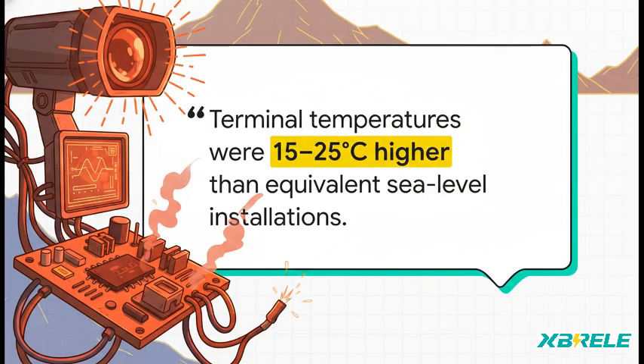And on the heat side of things, the evidence is just as dramatic. Thermal cameras at some of those Peruvian mines have shown that the exact same parts, under the exact same load, run 15 to 25 degrees Celsius hotter than they do down at sea level. That kind of extra heat just accelerates wear and tear, it loosens connections, and it's a constant threat to the whole system's reliability.